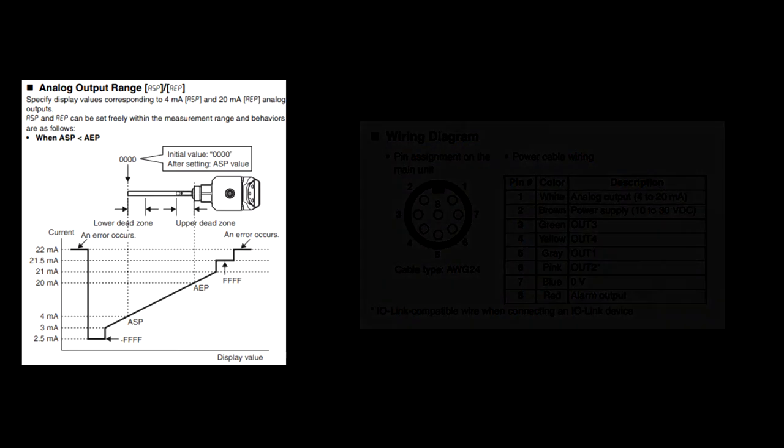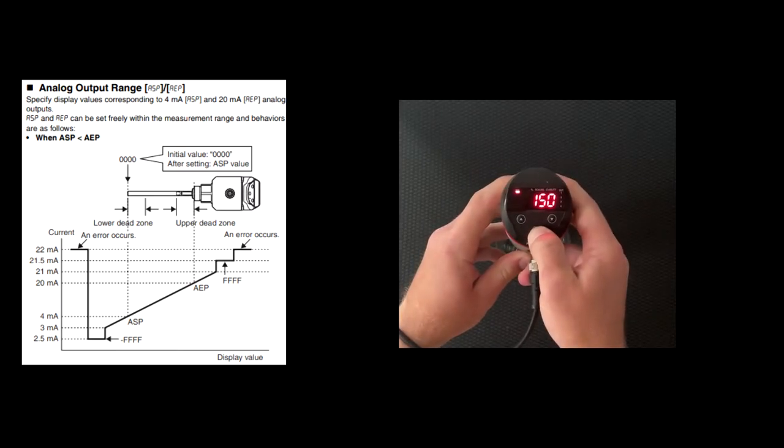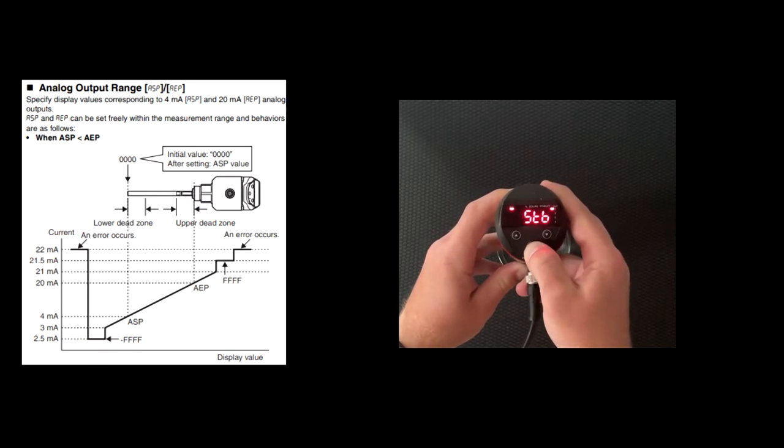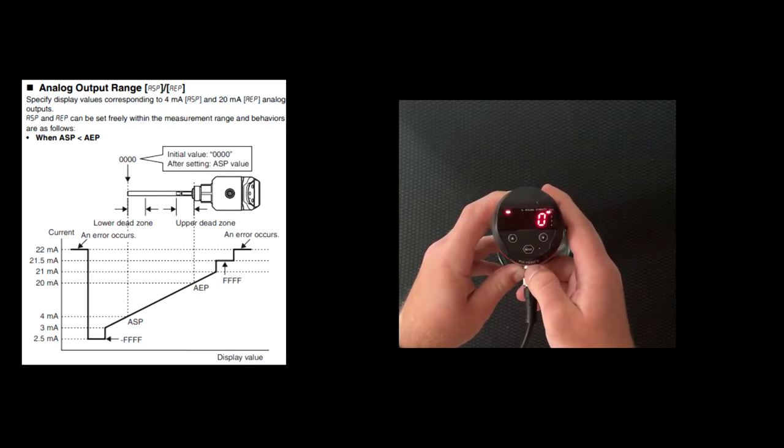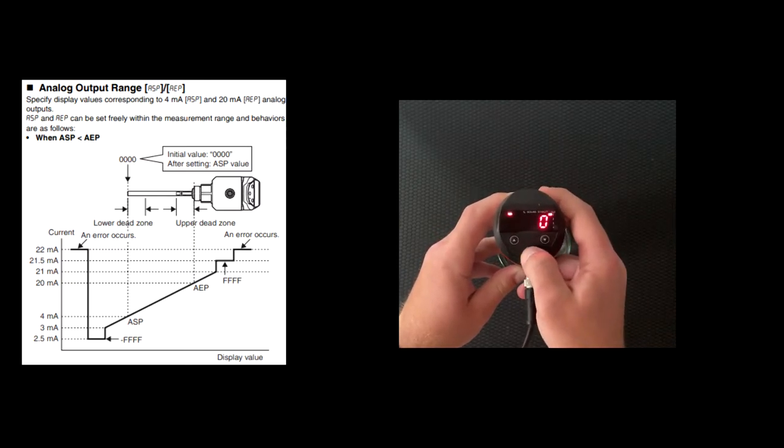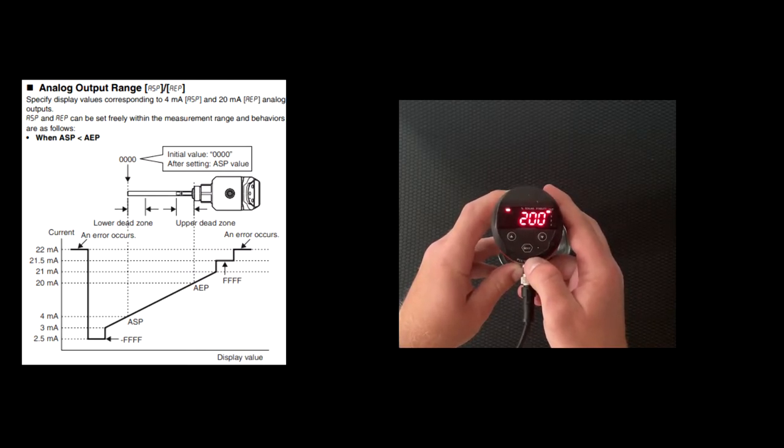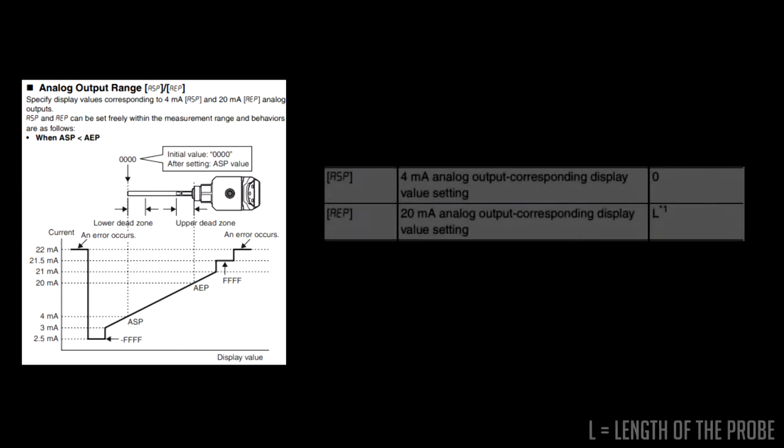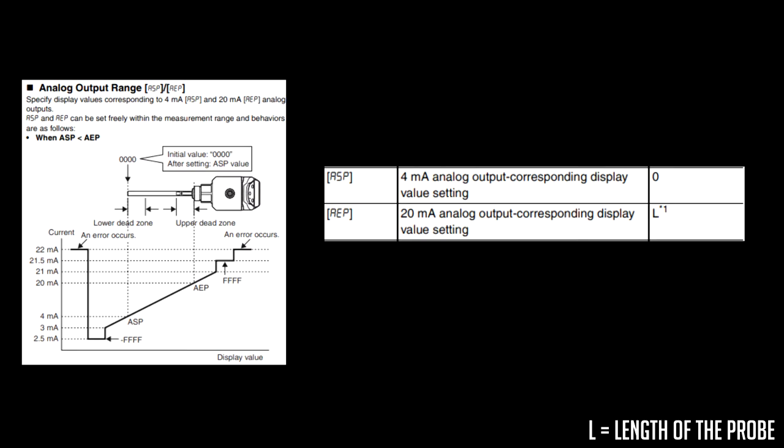Then, you'll just need to go into the basic settings, cycle through all the different menu items until you get to End, cycle over to EF for extended functions, and then cycle through past STB until you see ASP. ASP is going to be your 4 milliamp signal, and AEP, which will be just after that, will be your 20 milliamp signal. You may scale these however you'd like, but by default ASP, or your 4 milliamp signal, will be set to 0, and AEP, your 20 milliamp signal, will be set to the entire length of the probe.